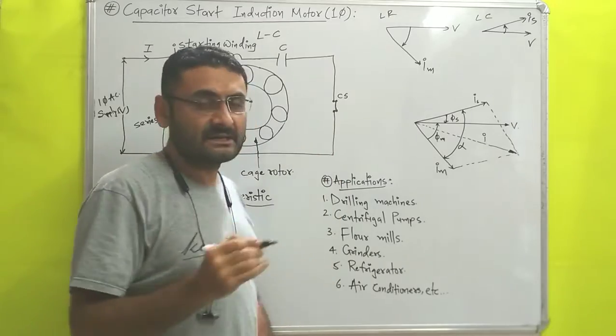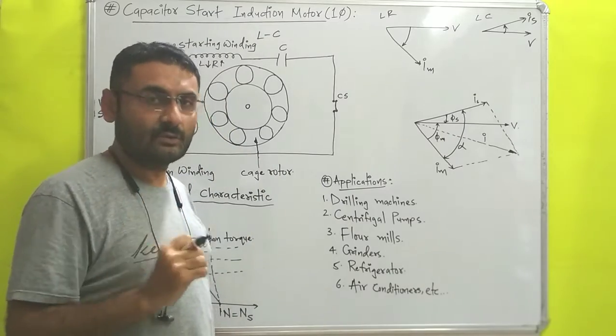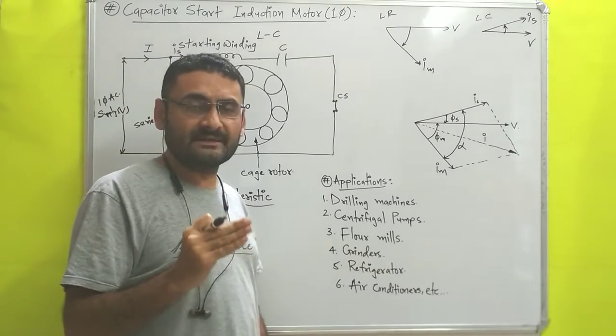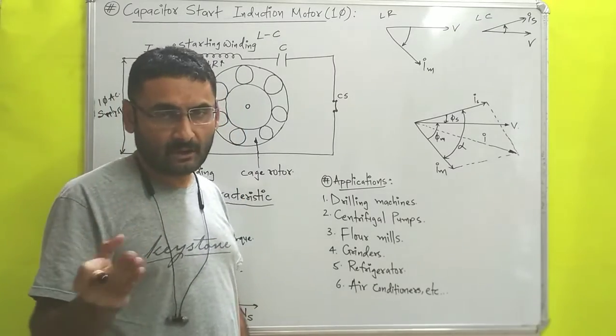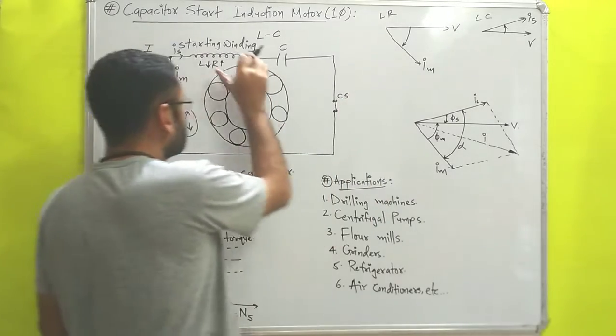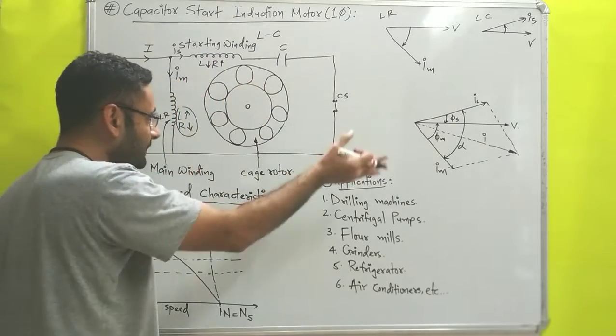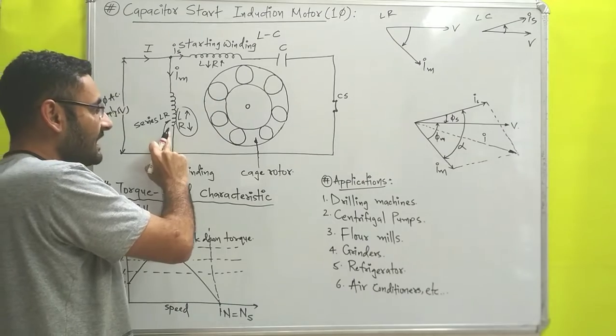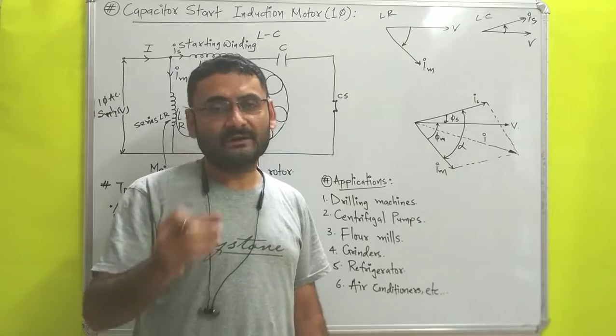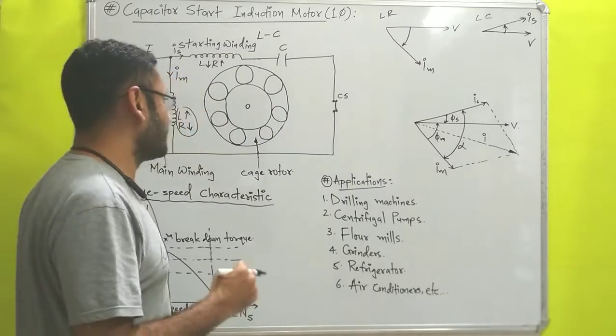One centrifugal switch is connected in series with the capacitor. This centrifugal switch is generally in the closed condition and it is an automatic switch. When the rotor starts to rotate and reaches up to 70% of its normal speed, the centrifugal switch will open, separating the starting winding from the main circuit. After that, the rotor continues to rotate with the help of the main winding only.